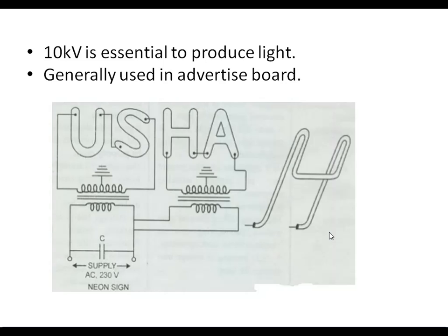The neon tube is used in varying lengths up to about 8 meters, and may be bent into almost any desired shape during manufacture. It consists of a length of glass tubing containing two electrodes, normally cylindrical in shape, of iron, steel, or copper. The tubes are mounted either on a wooden frame or a metal base. These are matched with a step-up transformer by connecting a suitable tapping for the rated current.